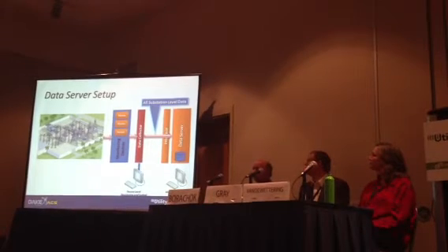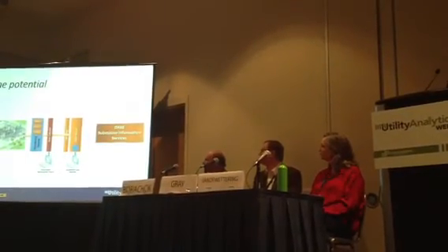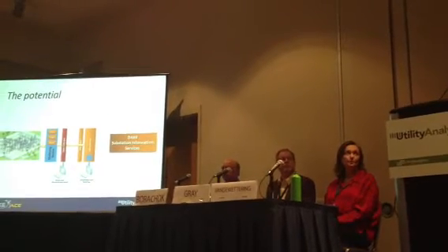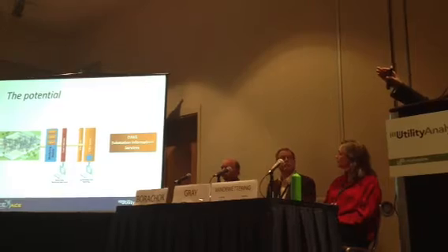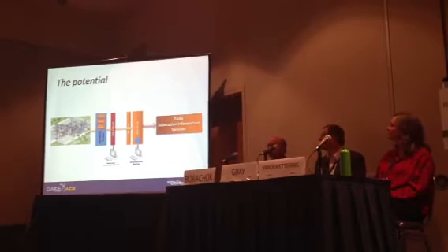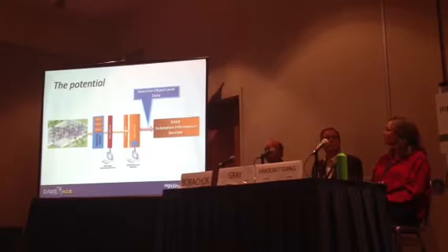But then we can take it further. We can say all substation level reporting can be done at a substation now with a data server existing. But that's not enough. So what is the potential? We've taken that setup and moved it further. We created a substation information services layer. This is completely CIM compliant, by the way, the Common Information Model compliant. So the data from the substation is set into CIM compliant structures, and then it's taken into the substation services. And this is now not everything, obviously, it is selective data.